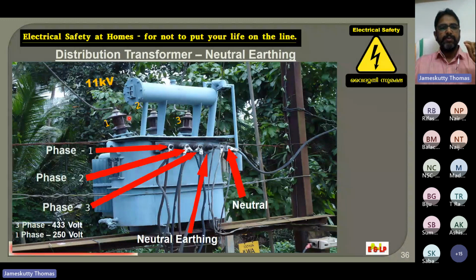Usually such a transformer will be rated 11 kV by 433 volt. It means if we are giving 11 kV supply on the primary side, we will be getting 433 volt on the secondary side. Another important point is that the same phases R, Y and B will be there at the primary and secondary. At the secondary side, the voltage between 2 phases will be 433. Remember, in the secondary, only 3 phases or 3 wires are there. Let us see how the 4th wire or the neutral is created.